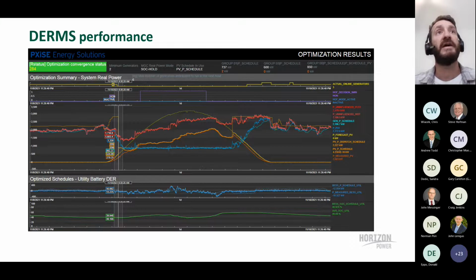We're curtailing quite heavily this day to meet the control objective of keeping 2 generators online at their minimum generator loading, which is 500 kilowatts per unit, so 1,000 kilowatts total. It's got to keep that hard line and not go below, and as you can see, it holds pretty steady across that point of interconnect.